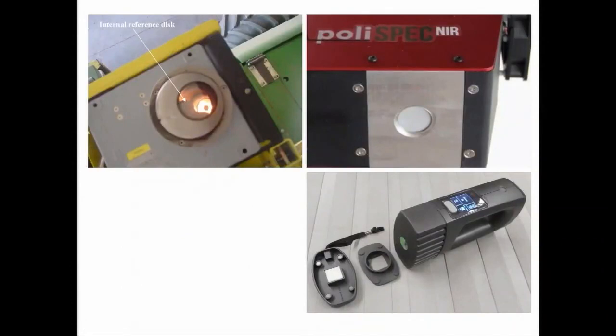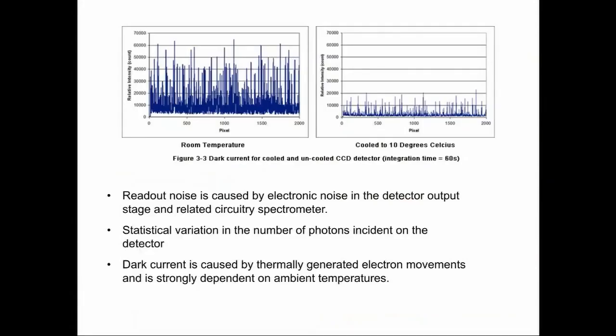The other instrument design consideration is how the instruments handle variability throughout the day. These light detecting diodes are subject to temperature variation. We can get something called dark current, where the diodes are actually also used for temperature measurement. If you've heard of something called an RTD, we look at the electronic signal developed by temperature variation in these diodes to measure temperature. So they can measure both temperature and light.